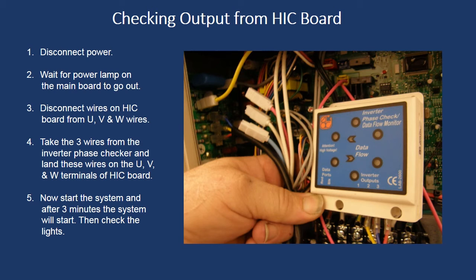Next, restore the power and make sure the indoor unit is calling for either cooling or heating. There will be a 3-minute delay before the HIC board sends the signal to the compressor. Pay attention to the lights on the inverter phase checker tool.